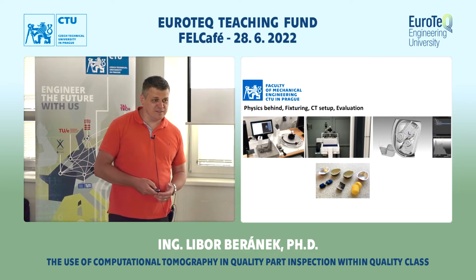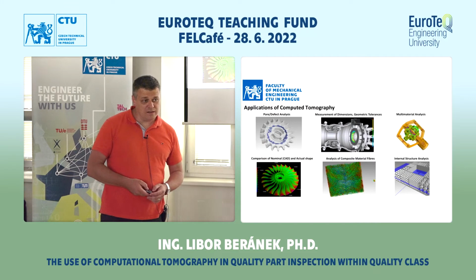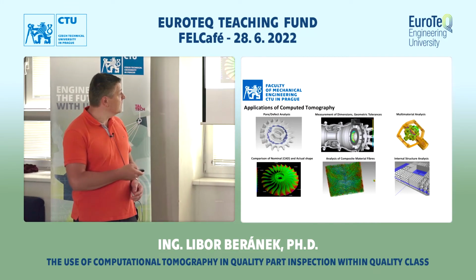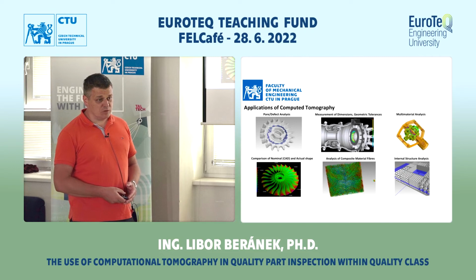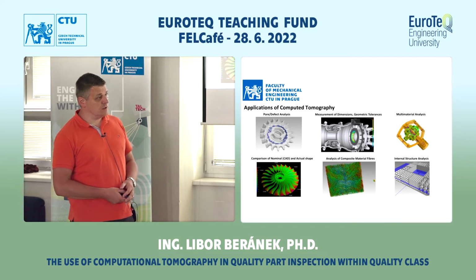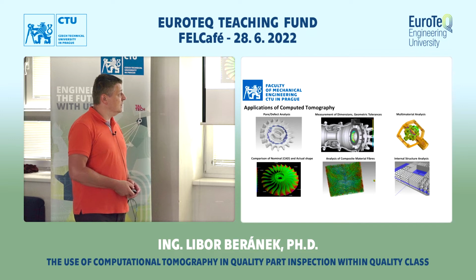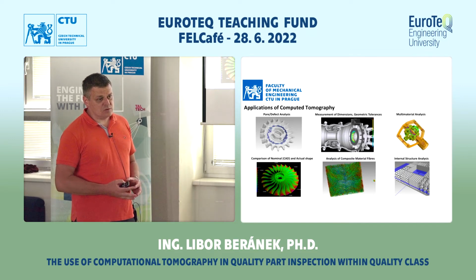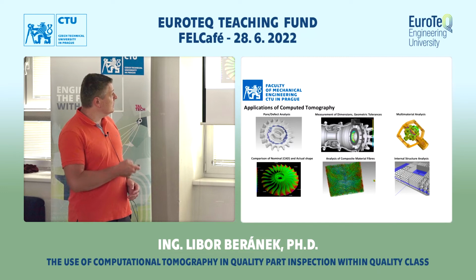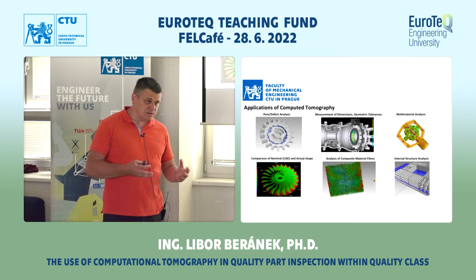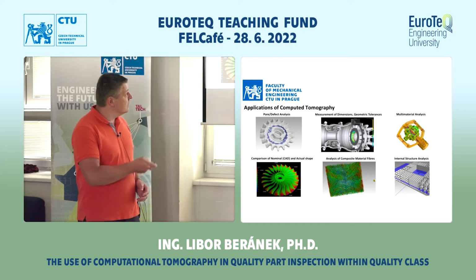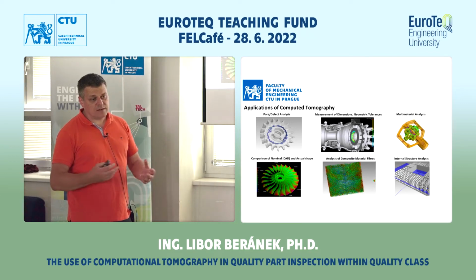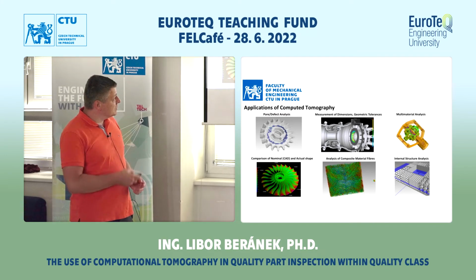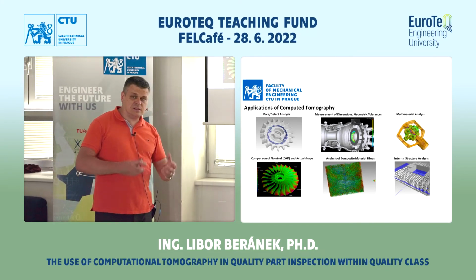So this is just really easy data to explain, but what analyses are required today? Typically, for casting and injection molding, you are searching for defects from the process, so you are searching for porosity. Because the CT we have is also a calibrated metrology machine, it may measure, as a traditional coordinate measuring machine, dimensions and form tolerances. Because it recognizes different density, you can do multi-material analysis, meaning you can separate different materials in a total assembly based on their density.